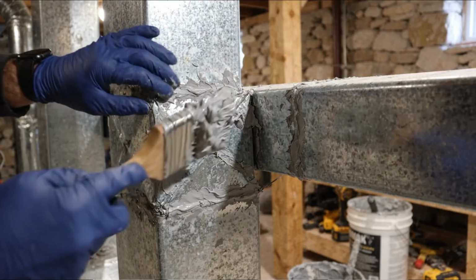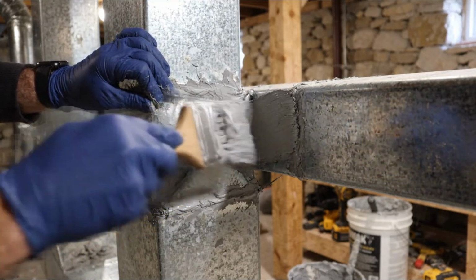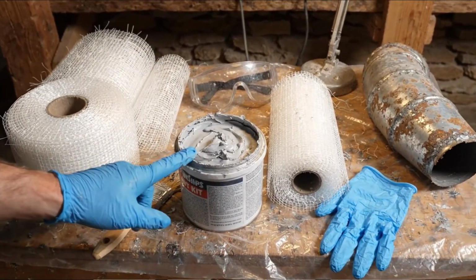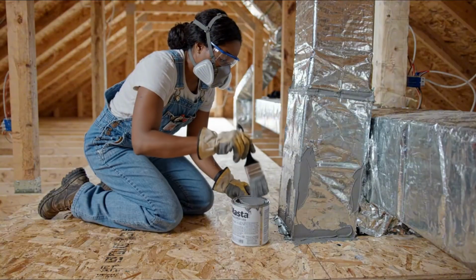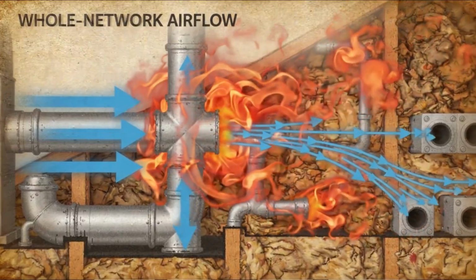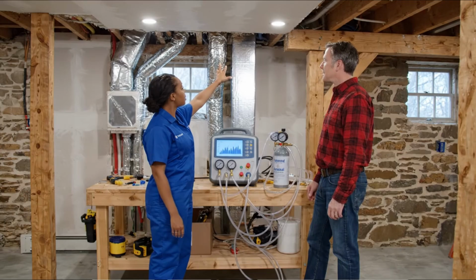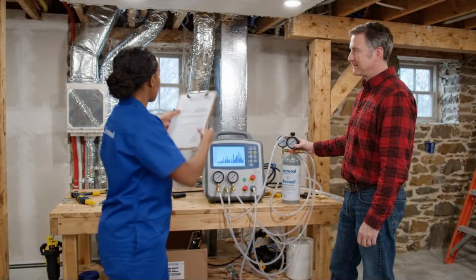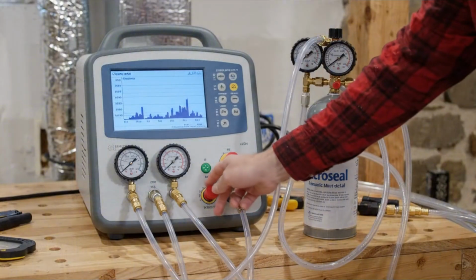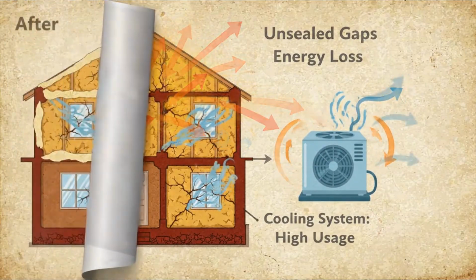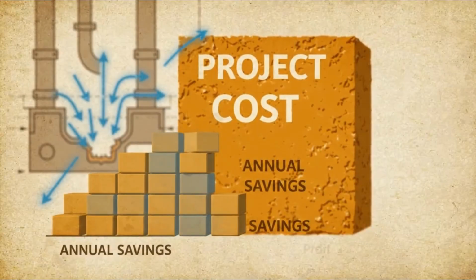Second priority, $85 to $300 depending on what you find. Accessible duct sealing. Mastic sealant on every joint, every seam, every boot connection you can reach. The materials cost under $100 for a typical house. The job takes a Saturday in the attic. Energy Star and Lawrence Berkeley National Laboratory documented average duct leakage at 20 to 30% of total airflow. If your weak register check found multiple rooms with poor flow, this is your second weekend project. For inaccessible ducts showing significant leakage, get an AeroSeal quote and a before and after test. The documented savings average $600 to $850 per year. Payback is 2 to 3 years.